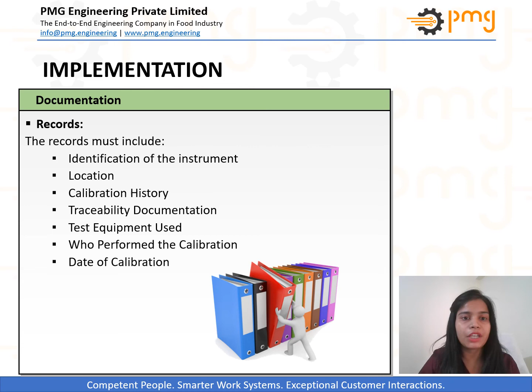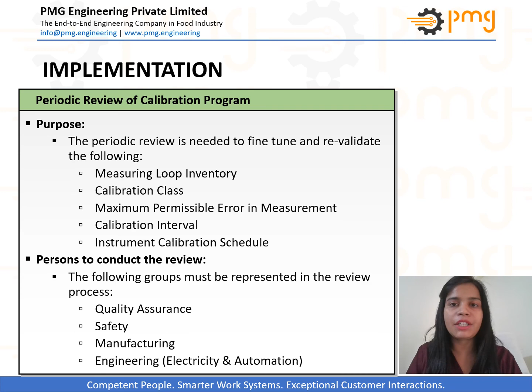Periodic reviews and training are very important factors for a successful calibration program. Reviews should reflect changes in facility processes, quality assurance, and preventative maintenance programs. Training is a requirement for maintaining personnel qualifications at an acceptable level. New and modified processes will require creation or modification of specific standard operating procedures. Periodic reviews will assure that changes to a single standard operating procedure have not created contradictions and discrepancies in the integrity of the calibration program.